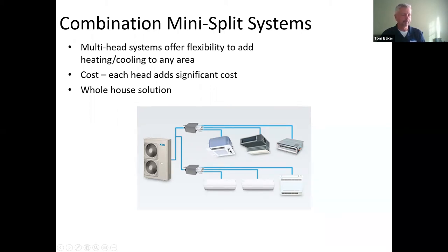You could also, if your home can handle it, if you've got the right structure, put the units up in the ceiling. So they're flush mounted to the ceiling where they're discreet, but they can still deliver the heating and the cooling from that vantage point. Or over here, you've got what's called a mini cassette that can go in the attic, and you can hook short ducted runs to it to deliver heat to smaller rooms.